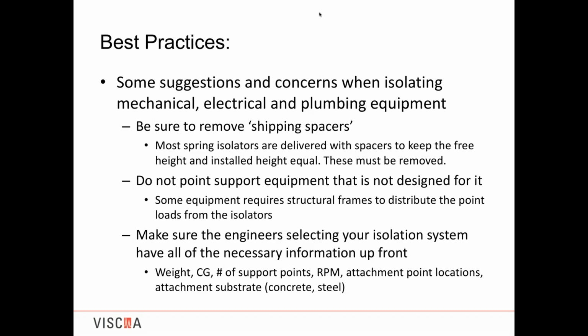Another issue we see, and I'll show it on further pictures, but you may have seen it or heard of them, there's shipping spacers. The housed isolators are typically shipped locked out with shipping spacers, such that the free height of the isolator doesn't change after you install it and adjust it, so all your piping and your plumbing into the equipment doesn't need to move. But you need to remove the spacers since they're short-circuiting your isolation. And every manufacturer has their own installation instructions. But most importantly, you should never remove any of the spacers until you can remove all of the spacers.